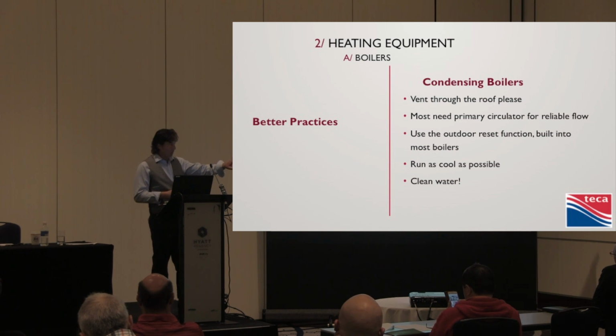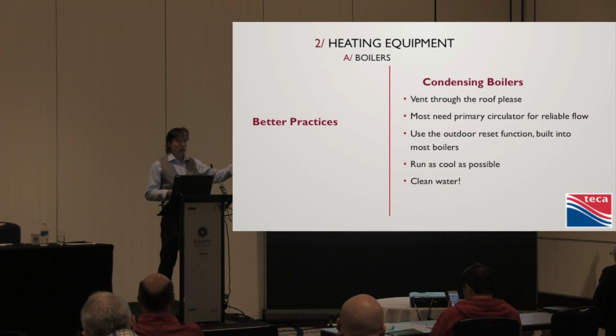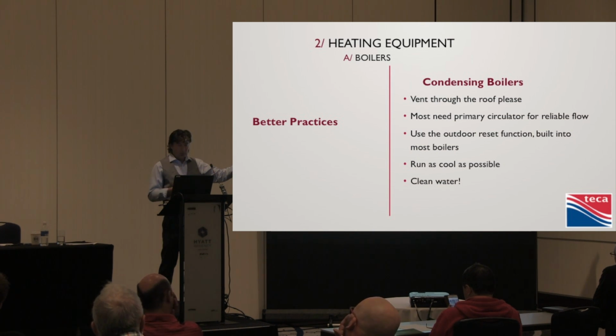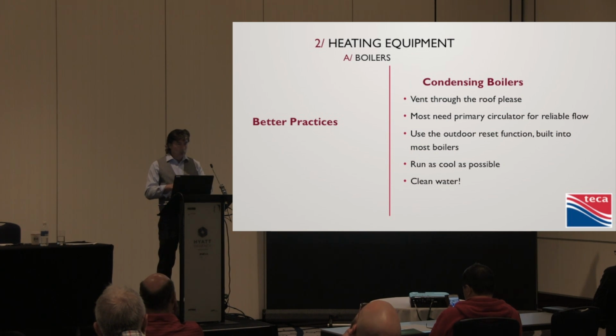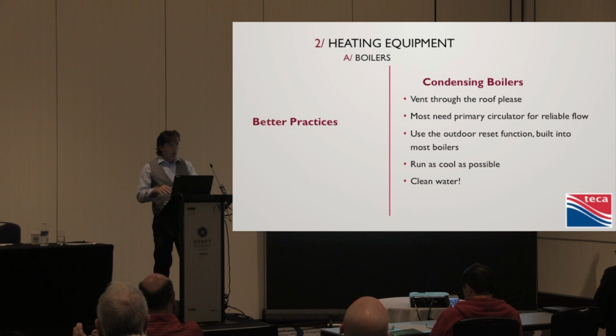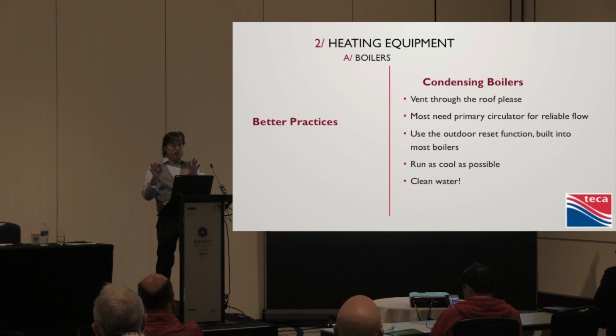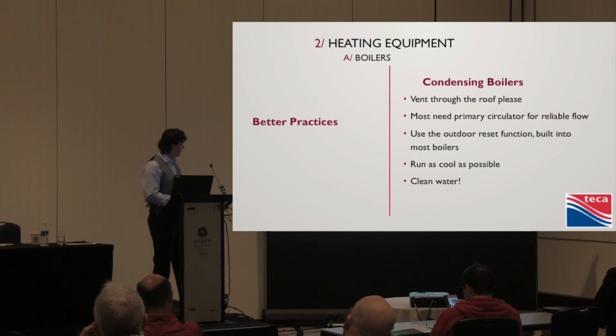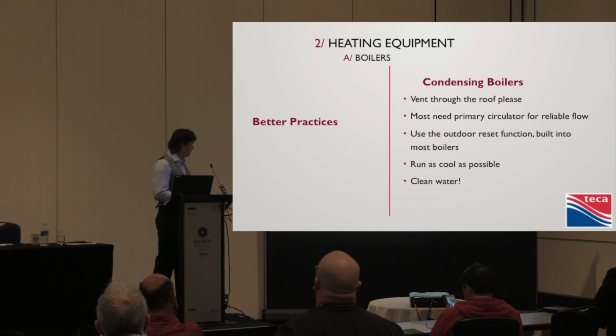So, for example, if I had a radiant wall, like I said, I've got to radiate heat through drywall. So I'm going to have slightly higher temperature, because I can probably get through this concrete floor easier. That underfloor stuff, we already said that's going to be hot as hell. So we need to circulate cooler water to the radiant floor and hotter water to the radiant ceiling or to a fan coil. That takes hotter water as well. So let's separate those loads. And when radiant calls, for God's sake, let's bring that nice cold water back. When the fan coil calls, okay, well, we send out the hotter water and we're condensing less. But do what you can to make sure that the system is running as cool as possible.